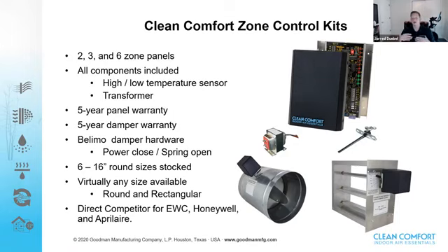When it comes to Aprilaire or Honeywell or EWC, they're all completely universal and interchangeable. So if you run out to a job and you find a damaged Honeywell damper, 2-wire damper, 24-volt damper on a system, you can use one of our Clean Comfort dampers to replace it with. Flip side with the panel. If you have existing Honeywell dampers and you want to swap out the panel with the Clean Comfort panel, you can do so. EWC, they're more known for the 3-wire dampers. You can use our Clean Comfort 3-wire dampers to change in and out with theirs. Fully universal, so it opens up a lot more market options for our contractors and distributor friends out there.